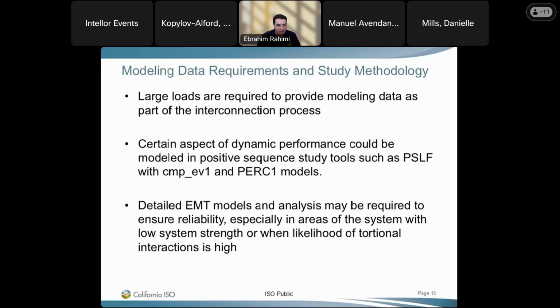For study engineers, certain aspects of dynamic performance of data center load could be modeled using positive sequence tools like PSLF, like CMP-EV1 dynamic model load, and very soon, if not already, PERC-1 model. They can capture some aspects of dynamic performance of the load. Beyond that, we may need detailed EMT models and analysis in certain areas if the system doesn't have enough strength compared to what is connected to it, or if a large data center load is close to synchronous generation with risk of torsional interaction. We may require EMT models and studies as part of that.